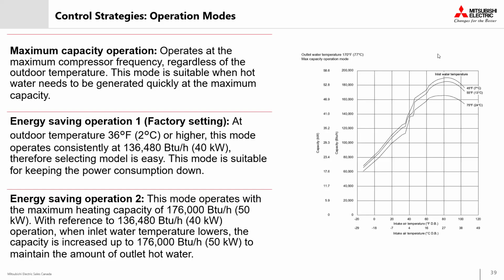And then generally, a lot of manufacturers will also offer energy saving modes. These modes will intentionally limit the system's maximum output, especially when outdoor temperatures, like I mentioned earlier, are quite mild in the summer months, but the demand is relatively low throughout the building. So by operating at a fixed or reduced capacity, the unit can deliver excellent efficiency and keeps those operating costs and carbon emissions in check.